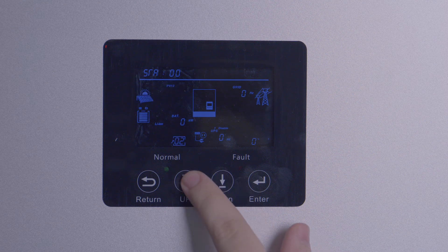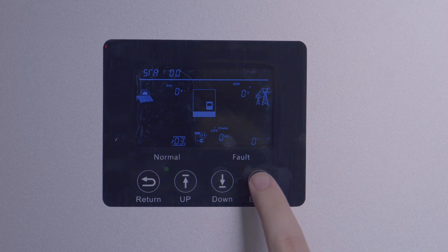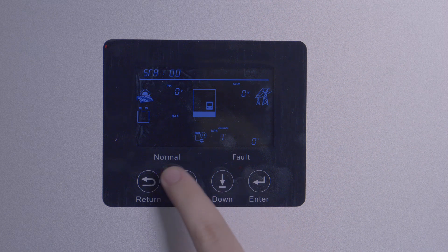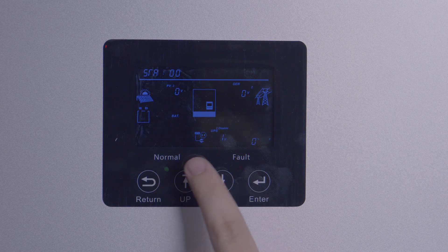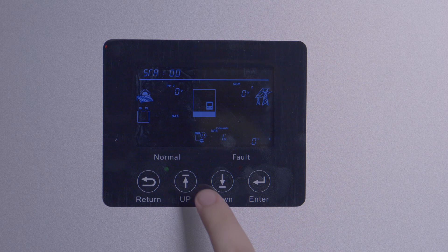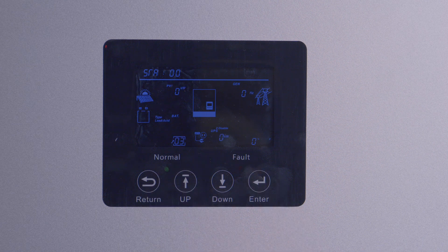Setting three, battery type, is very important. This can be set to lead acid, which doubles as open loop lithium; Li-ion, which is the closed loop lithium setting; and no batteries, which is very niche and not recommended for normal operation.